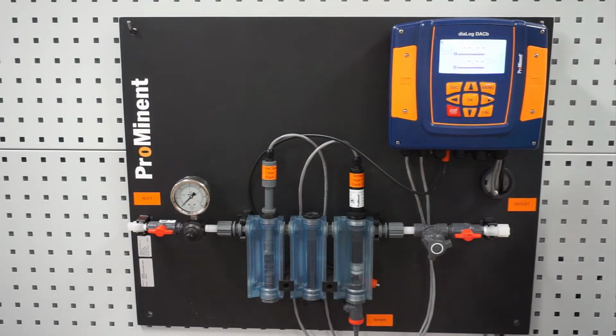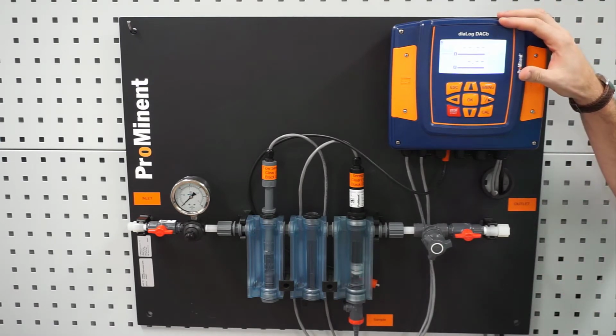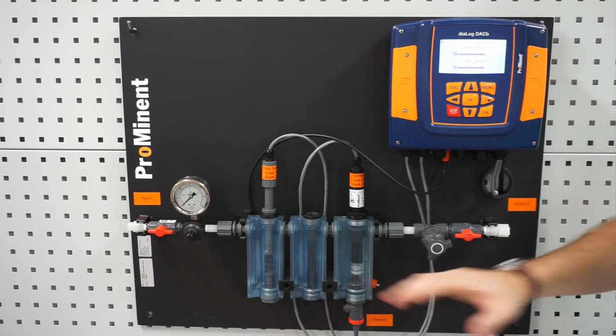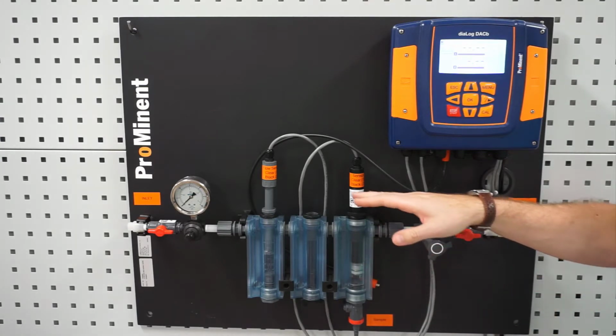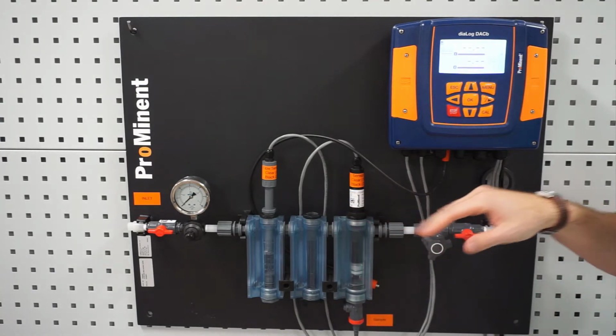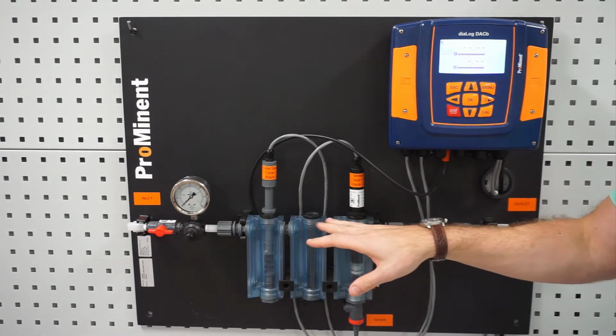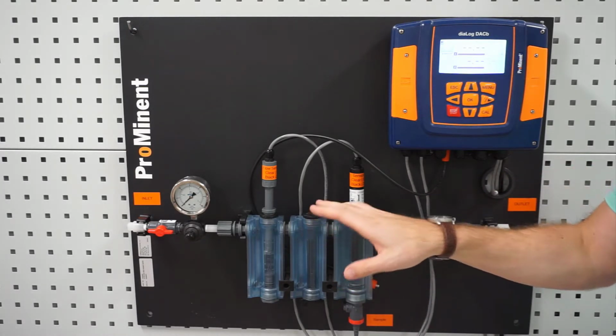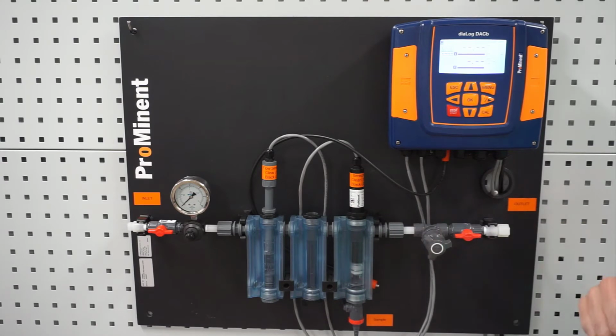Prominent controller packages come pre-wired and pre-programmed from the factory. I'm going to walk you through the process of starting up a package. The package we have here has a DACb controller on it, and with that controller we are going to be looking for the free chlorine. And with the free chlorine we also need to make sure we have a pH sensor to compensate for our free chlorine reading.